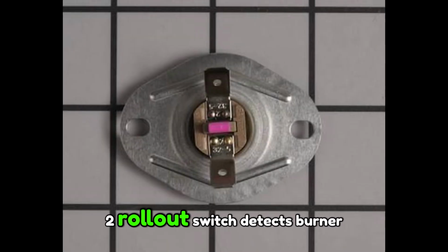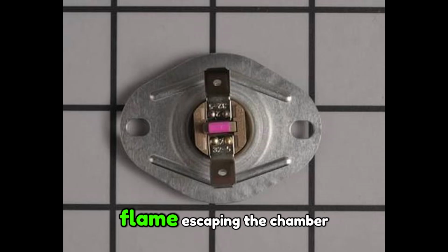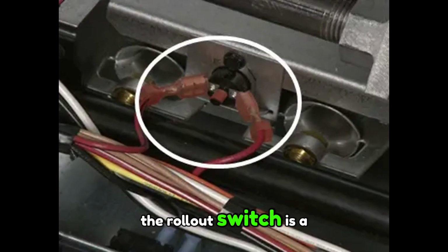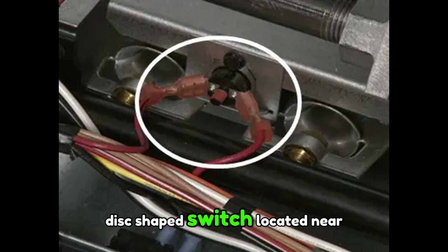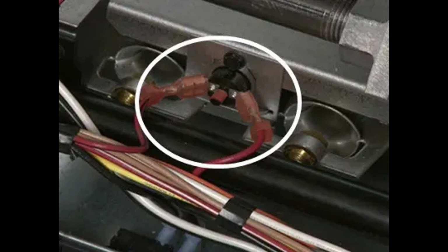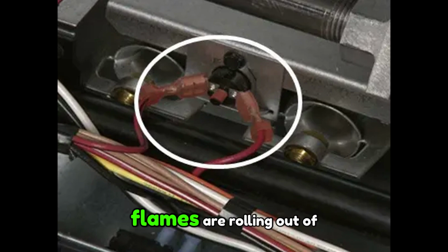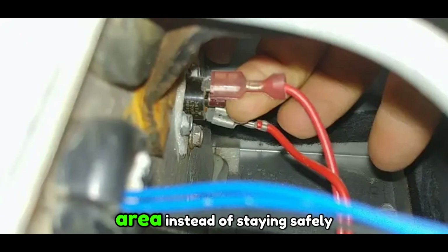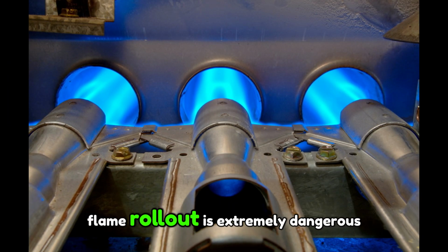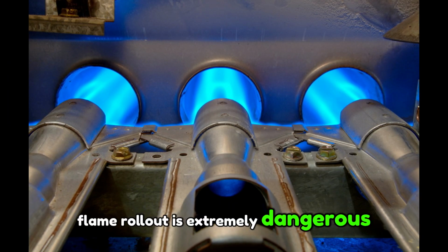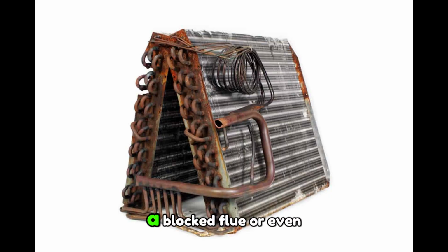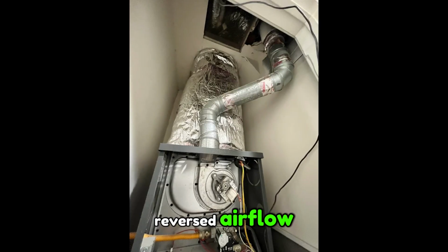2. Rollout switch detects burner flame escaping the chamber. The rollout switch is a small disc-shaped switch located near the burner compartment. Its job: to detect if flames are rolling out of the burner area instead of staying safely inside the heat exchanger. Flame rollout is extremely dangerous. It could mean a cracked heat exchanger, a blocked flue, or even reversed airflow.